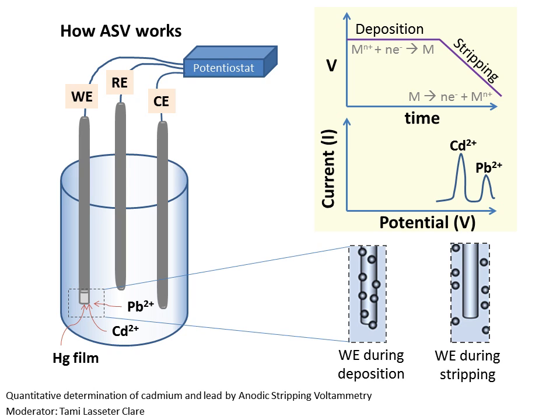The counter electrode is where current is actually measured, and that current is proportional to the concentration of the metals in your sample. Current is what is being measured, but voltage is what you use to get the chemistry to happen. Imagine that you have a cup with a small amount of liquid — that will define your cell. The actual cell is quite compact with a little stirrer in the middle of it.